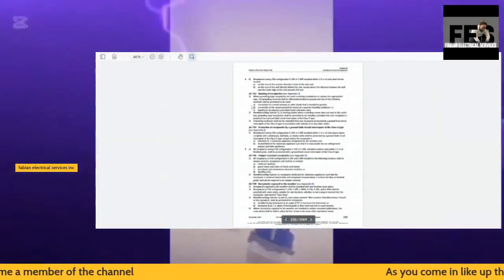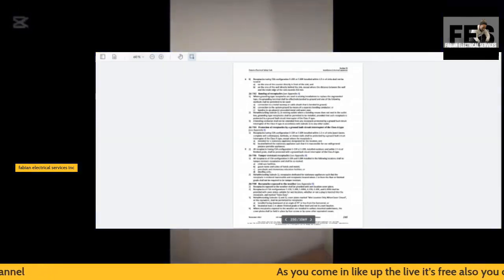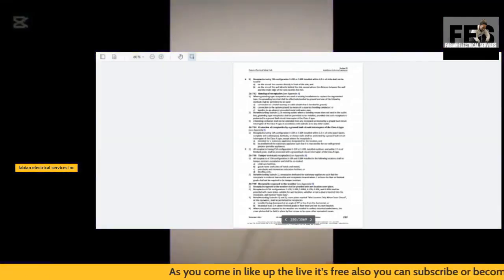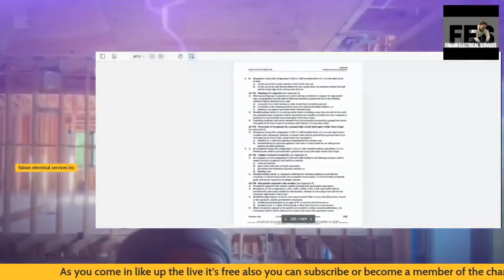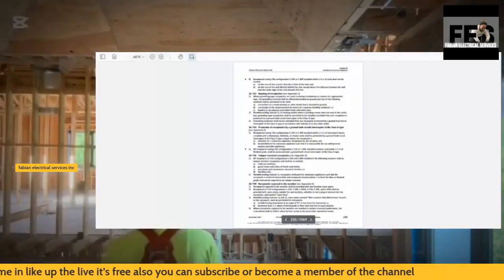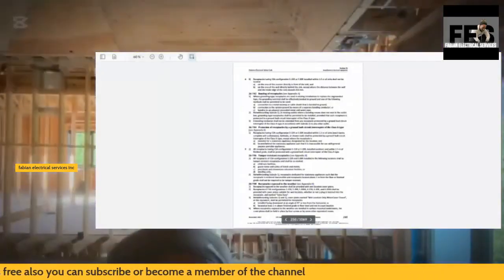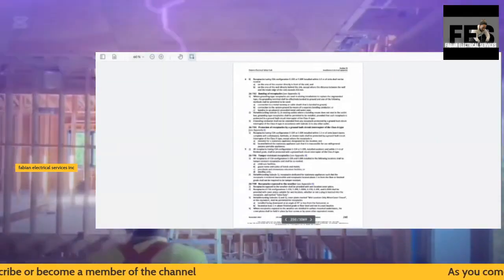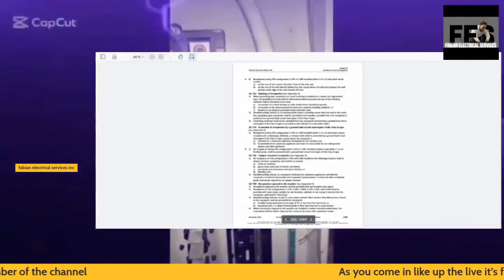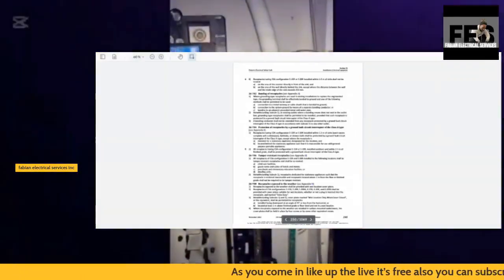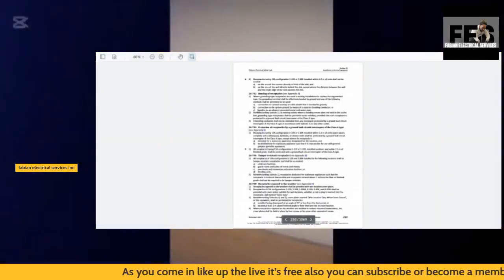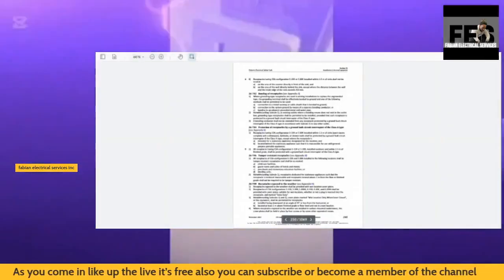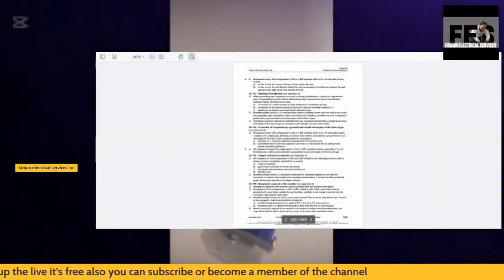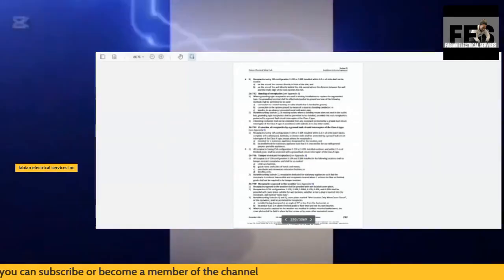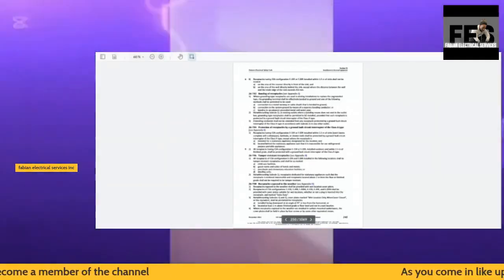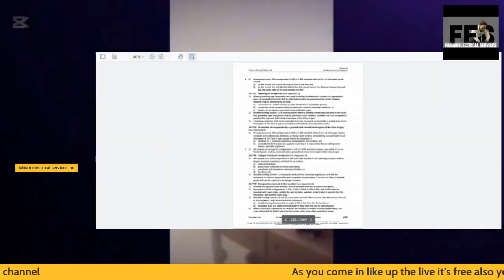And what this simply means is that a lot of times you go into homes, and they don't actually have a ground to the receptacles, and you can simply get the ground to the first point by means of connection to a metal raceway or cable sheath that is bonded to ground, by means of connections to the system ground, by means of a separate bonding conductor, or bonded to an adjacent grounded metal cold water pipe, which is what I have done before.